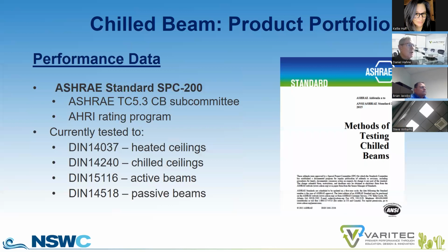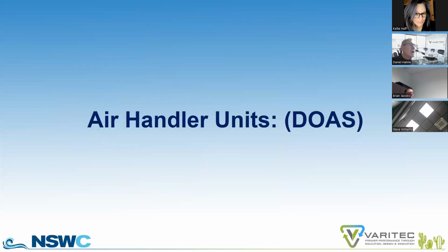to optimize performance in an underfloor system. Please be aware that if you're selecting chill beams, the manufacturer you might be working with is certainly in intent of following their testing methodology as described by ASHRAE Standard SPC 200. I was actually a voting member on that committee. What it does for chill beams is what AHRI does for chiller and coil performances. It standardizes a testing methodology so that everybody can rest assured that the performance published by those manufacturers is based on that testing methodology and not some invention of their own. So talking about chilled beams, let's move on to the air handler component.